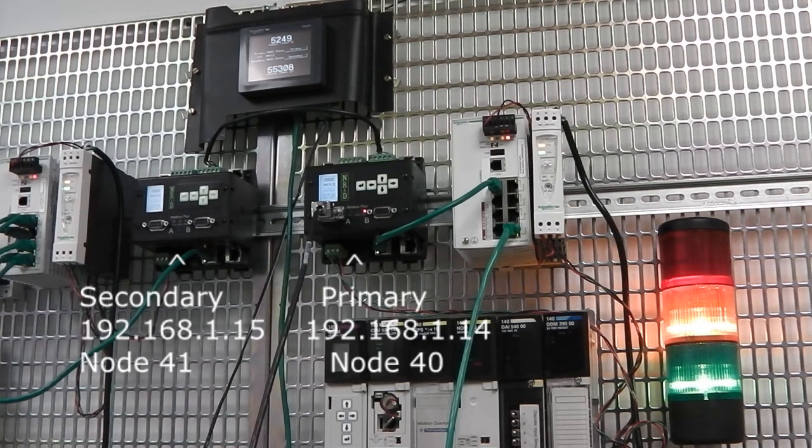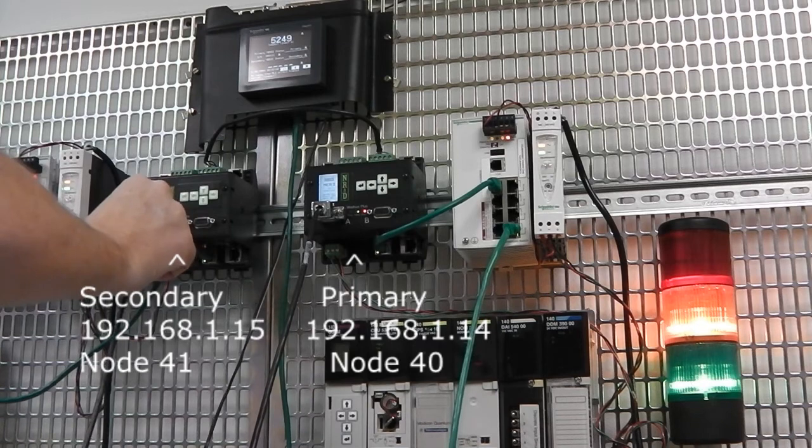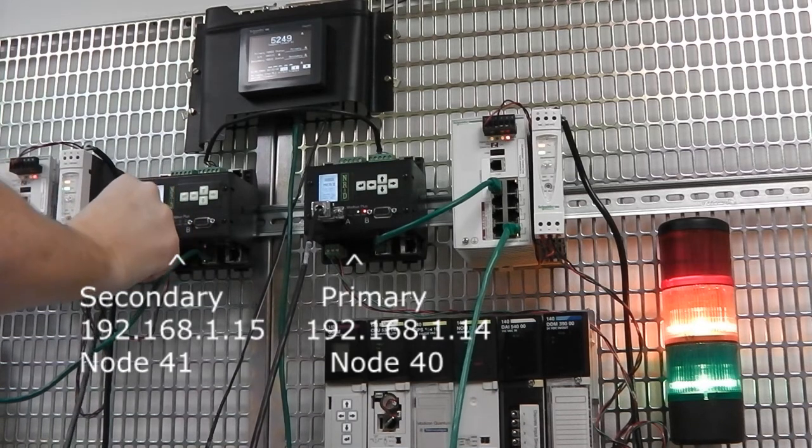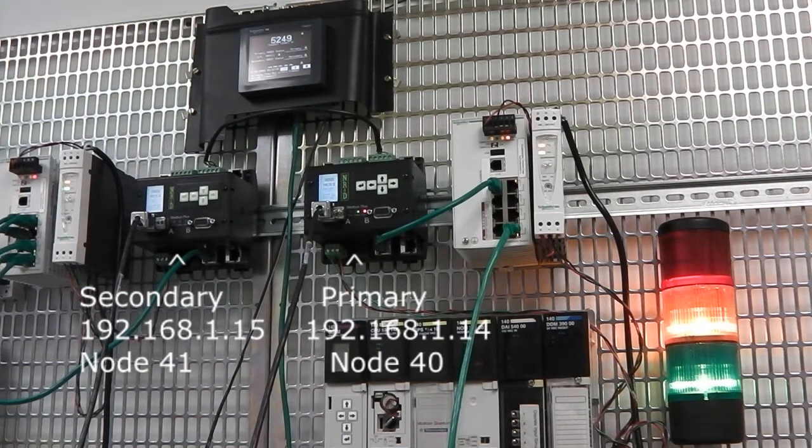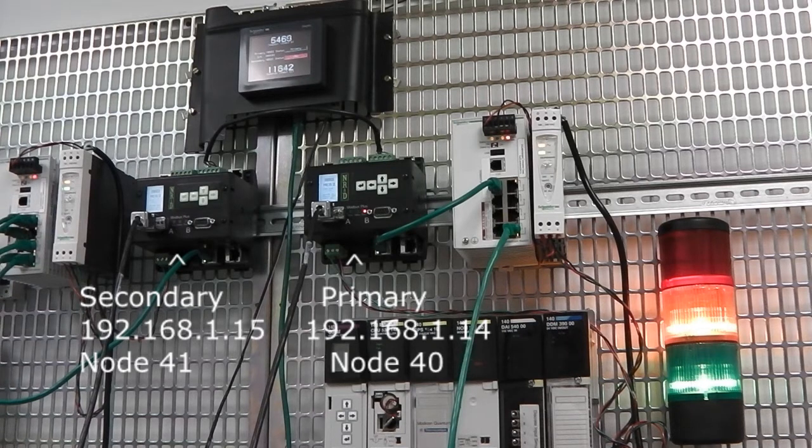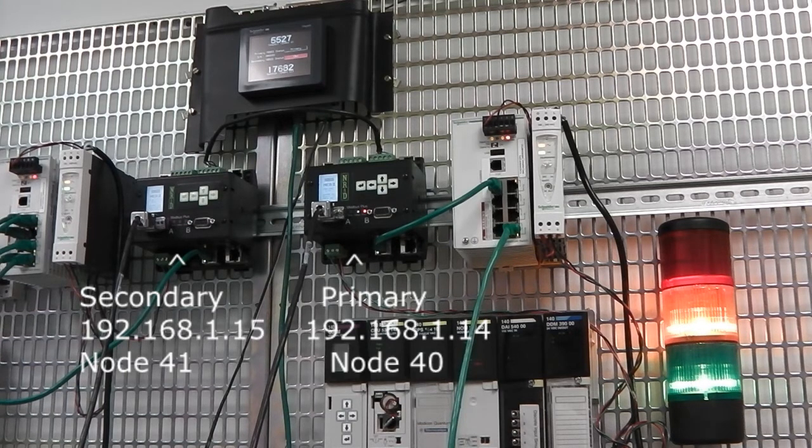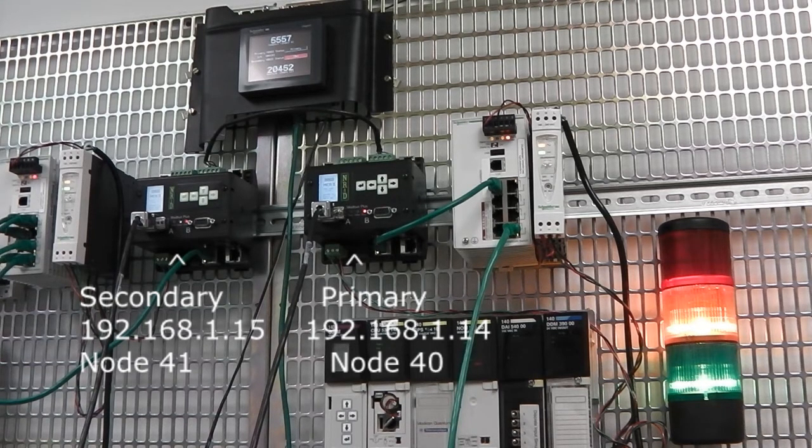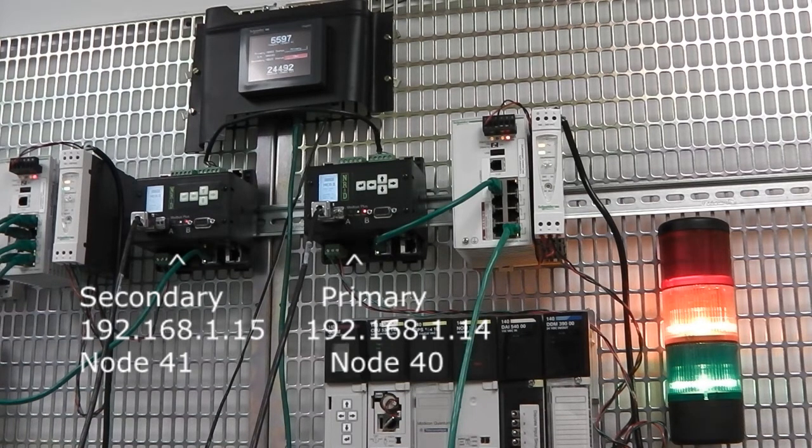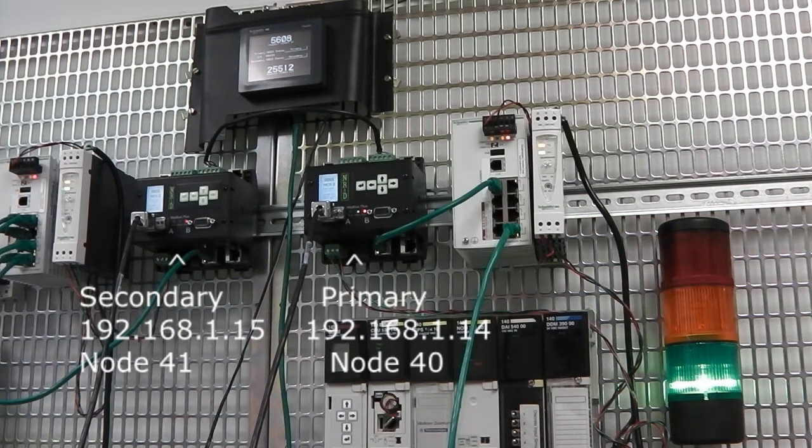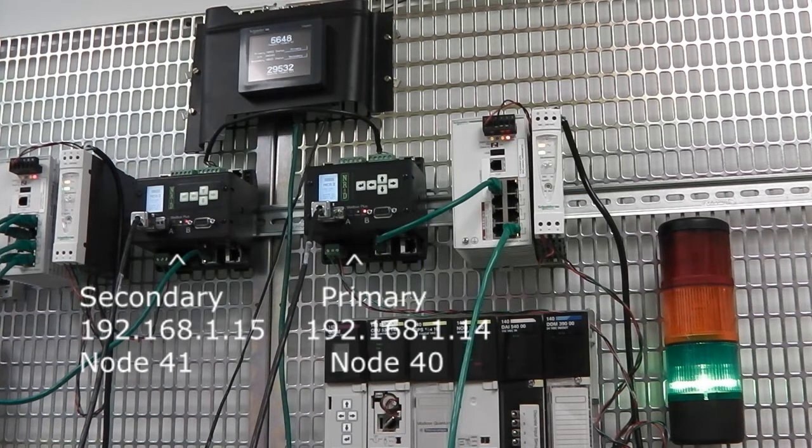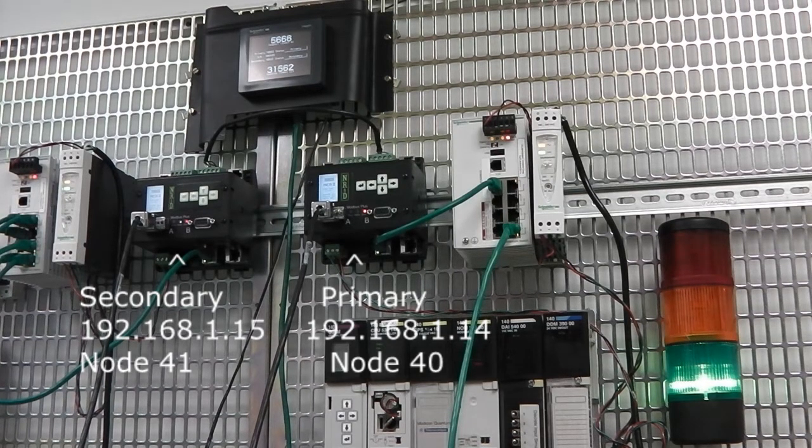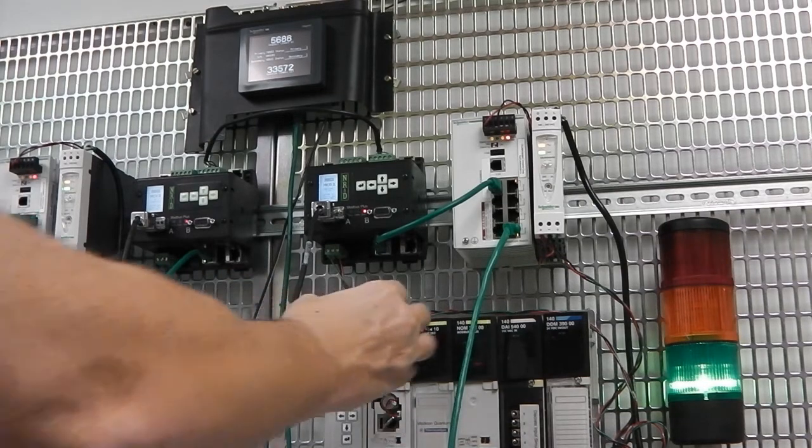Causes for automatic transfer include loss of Modbus Plus on the primary, loss of Ethernet link on the primary, loss of power on the primary, and mismatched MEB firmware. Transfer can also be triggered via Modbus communications. The typical downtime during a transfer is about 16 seconds.